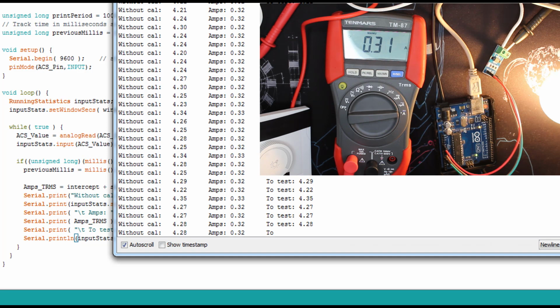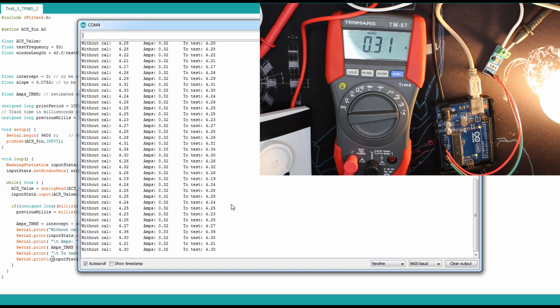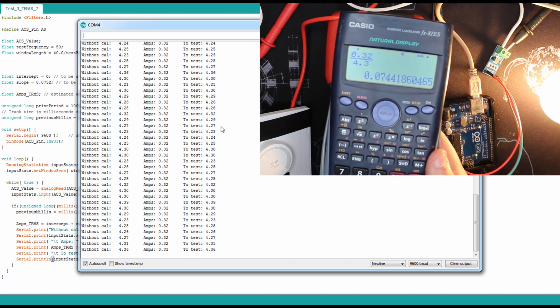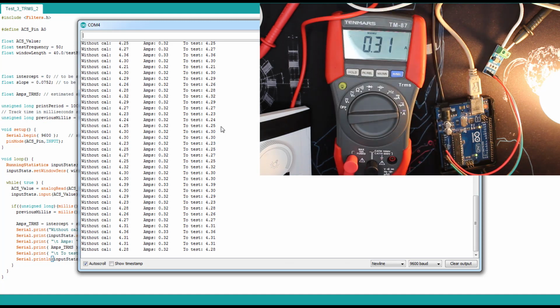It requires just a little calculation. So to get the slope value, all you have to do is divide the correct value by the value you got. So here the correct value is 0.32, we divide it by 4.3 for example. And here, as you can see, our slope is 0.0744. The slope I found yesterday is 0.0752. This is how you get the slope, and you place it over there.